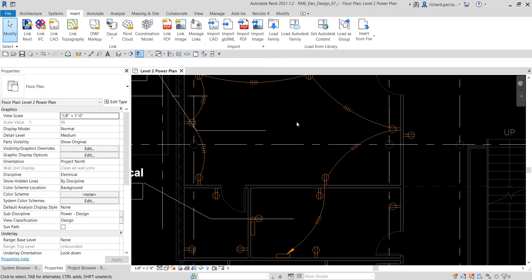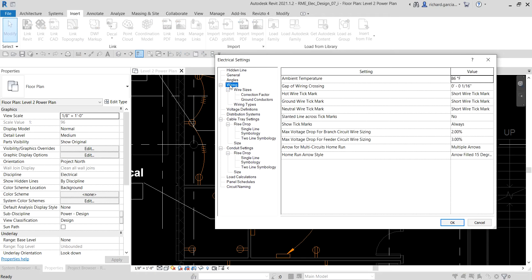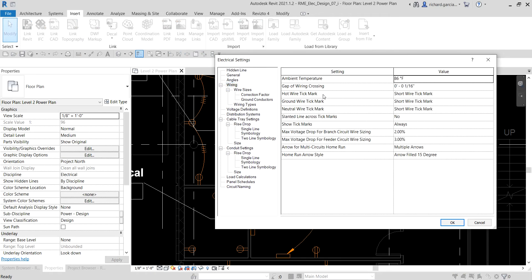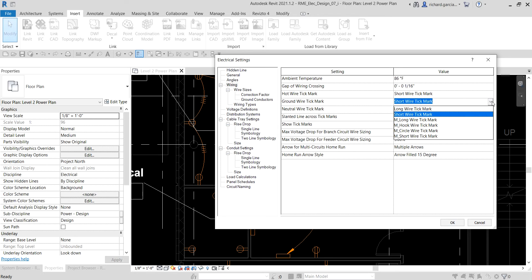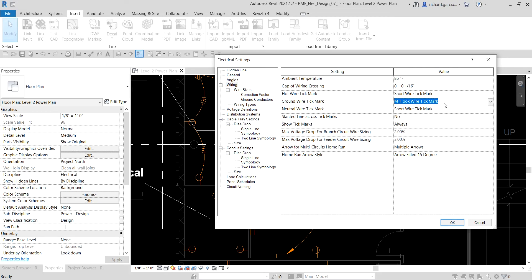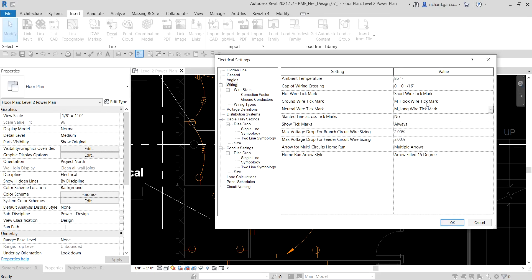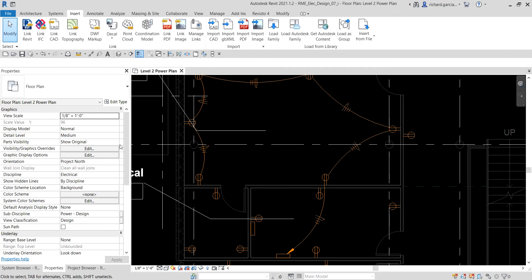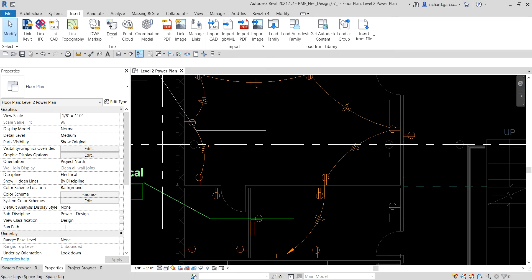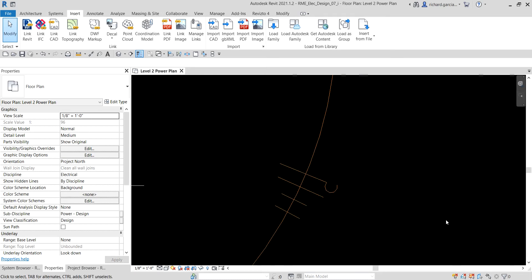To change the tick mark type, go back to Electrical Settings — you can type ES — then go to Wiring. You can change the tick mark value for each conductor type. For my ground wire tick mark I'll change it to Hook Wire Tick Mark, and for the neutral I'll change it to Long Wire Tick Mark. Select OK. As you can see, the tick marks have changed — ground conductors now display as hooked tick marks and neutral conductors display as a long tick mark.